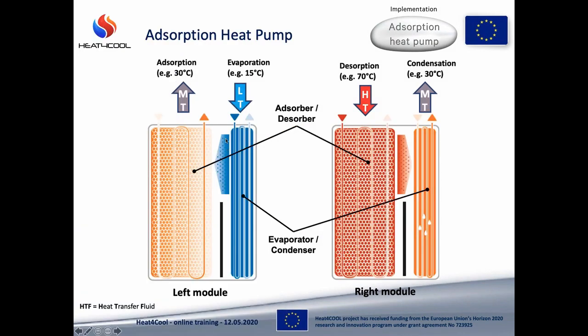Here in this slide, on the left-hand side, you can see the adsorption-evaporation phase. As you know from the previous slides, in the adsorption process, the heat is released to the ambient. Therefore, we need HTF at medium temperature level, MT, circulating through the adsorber, cooling it down. On the other hand, the evaporation process collects the heat from the HTF. That's our cooling effect. And HTF at low temperature, LT, circulates through the evaporator.